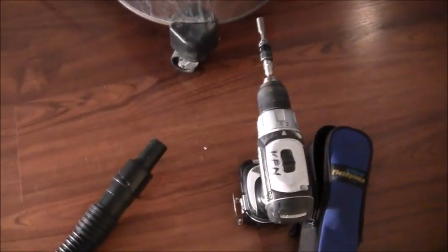So I took this and put it on blow mode, and blew out as much as I could. What you're trying to do is get the dust out of this motor so it can breathe and not overheat. Dust will overheat these motors, so you look at your windings down there and just try to keep everything clean.